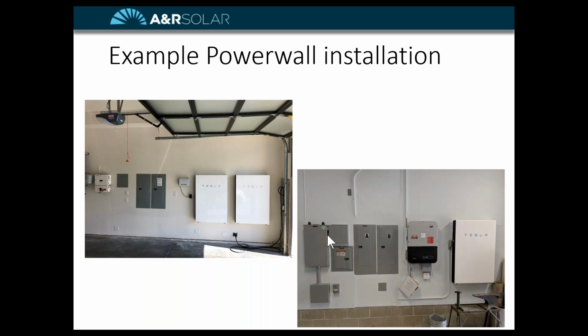We want to keep the gateway and put the equipment as close to the meter as possible, usually, because that's usually where the panel is. Sometimes you have a panel on the inside of your house, like my architect buddy, his interior to his house. I said, we're not going to try to do a protected loads panel, we're just going to back up your whole house. And it was easy access from the outside, so we could back up everything in his home.